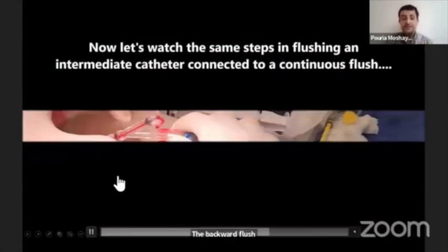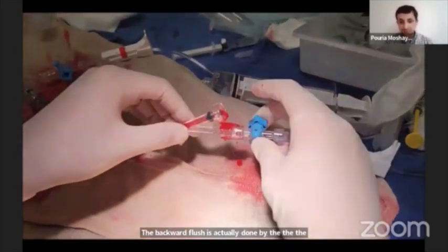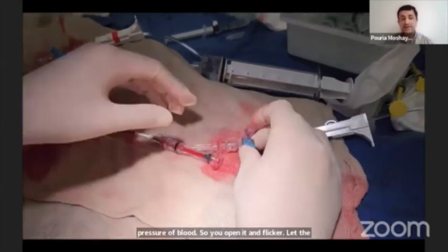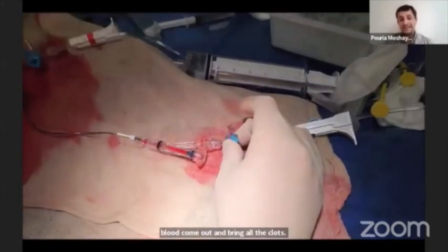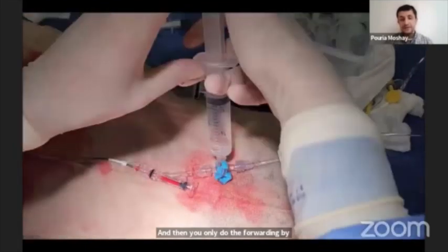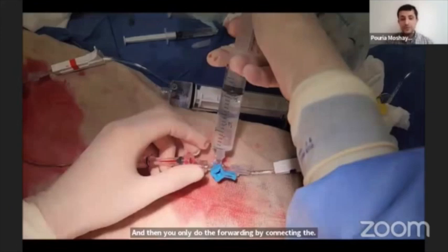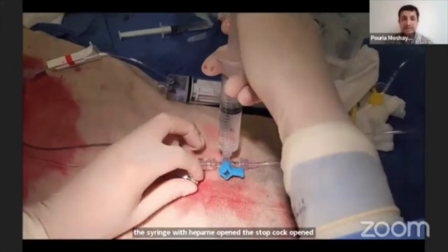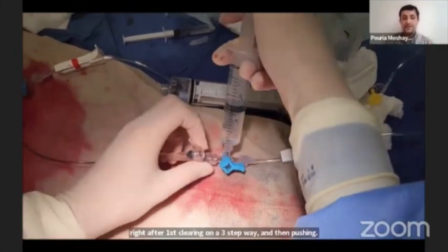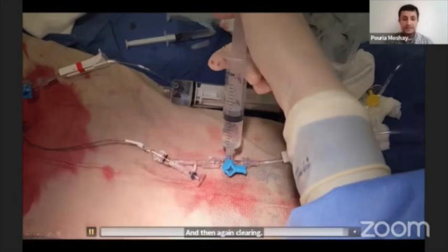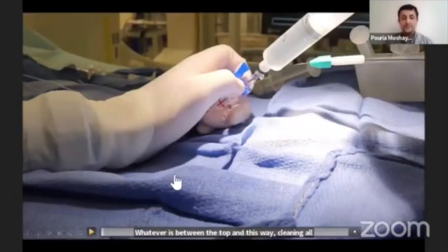The backward flush is actually done by the pressure of blood. So you open it and flicker, let the blood come out and bring all the clots. And then you only do the forward flushing by connecting the syringe with heparinized saline. Open the stopcock, open the wide adapter, first clearing in a 3-step way, and then pushing, and then again clearing whatever is between the stopcock. And this way, cleaning all the air and clots that could be there. Believe me, there are several times I actually pulled out clots that I would otherwise have pushed and caused stroke.